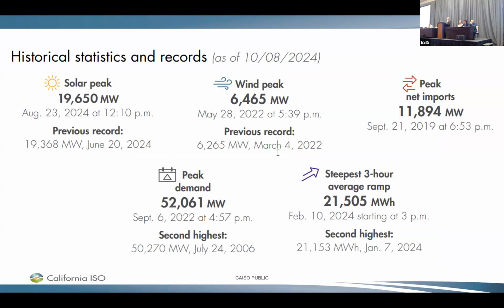Back in February of this year, before we hit our peak solar, as has been talked about in some of the other presentations, with the large concentration of solar, if you're looking at net load, it displaces a lot of the traditional resources. But then in the evening when that solar ramps down, you have to replace it with other resources. We did have a 3-hour ramp of over 21,000 megawatts within 3 hours. So a lot of ramping capacity has to be installed and available, not just megawatts, but megawatts per minute.